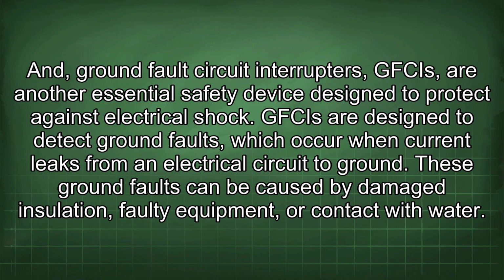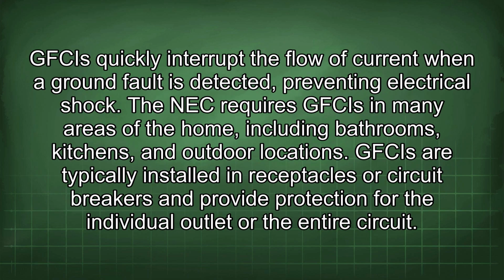And ground fault circuit interrupters (GFCIs) are another essential safety device designed to protect against electrical shock. GFCIs are designed to detect ground faults, which occur when current leaks from an electrical circuit to ground. These ground faults can be caused by damaged insulation, faulty equipment, or contact with water. GFCIs quickly interrupt the flow of current when a ground fault is detected, preventing electrical shock. The NEC requires GFCIs in many areas of the home, including bathrooms, kitchens, and outdoor locations. GFCIs are typically installed in receptacles or circuit breakers and provide protection for the individual outlet or the entire circuit.